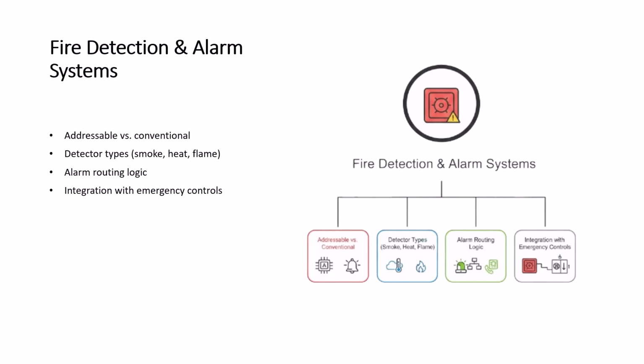Then we have the detector system. Majorly two detectors are used: smoke detector and heat detector, along with the fire alarm system. Then comes the alarm routing logic, which defines the routing of our fire alarms and what should be the plan. Then there is integration with emergency controls and our BMS. In emergency controls, we can also integrate our alarm system directly with the local municipal council, the fire brigade system, and emergency response teams at the national level. So once there is an unusual event, it is automatically notified to government officials as well.